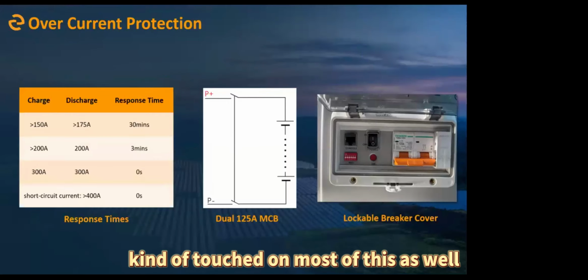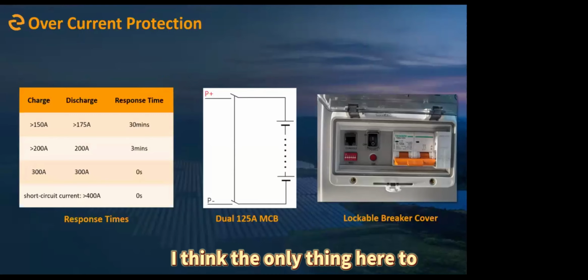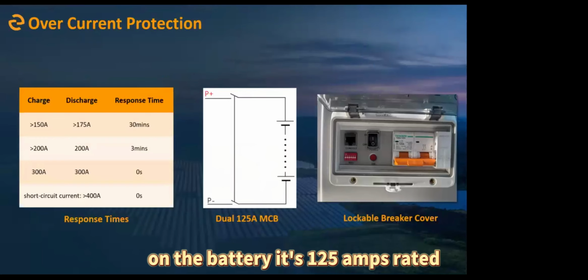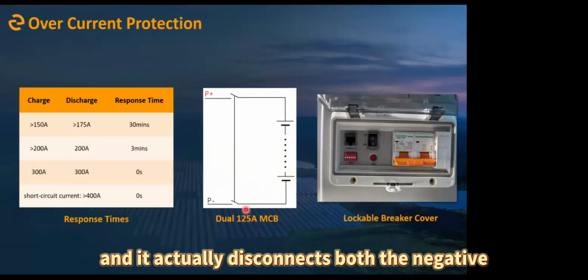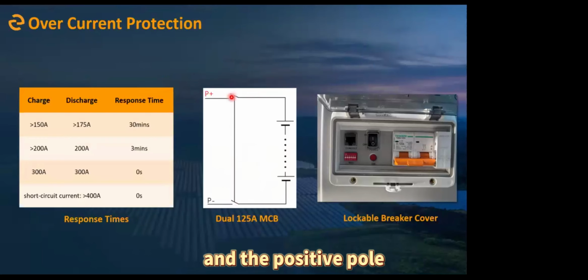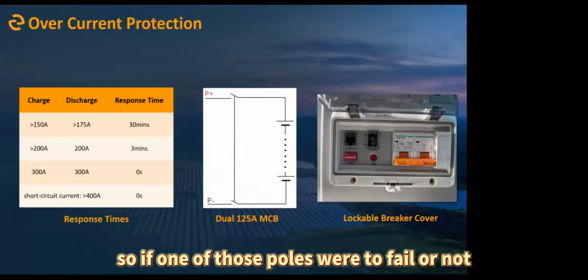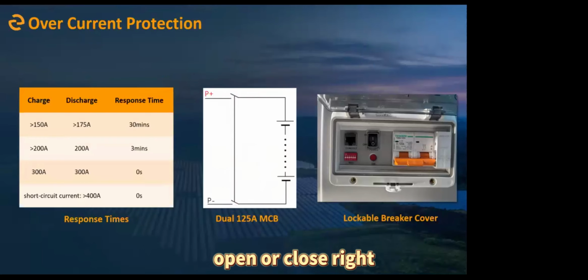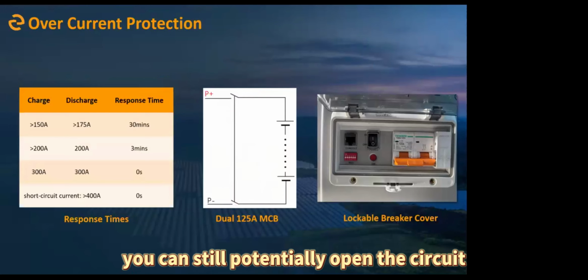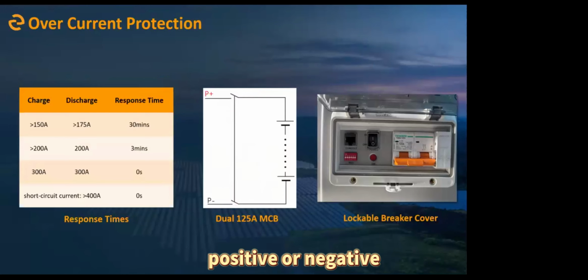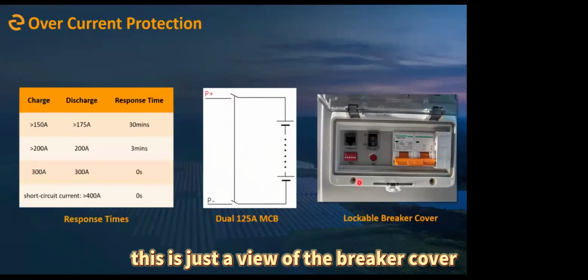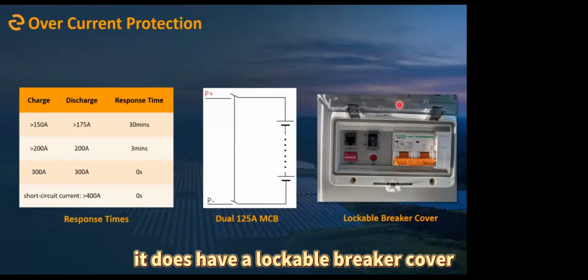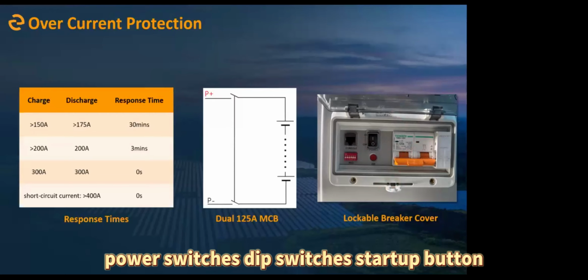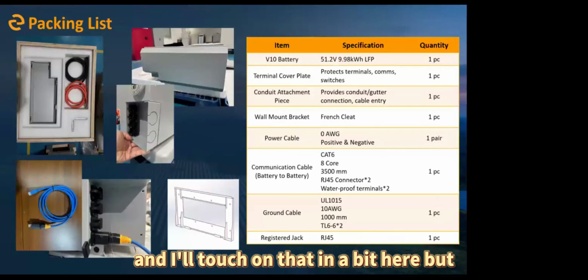Kind of touched on most of this already. I think the only thing to recap here is the circuit breaker on the battery. It's 125 amps rated, and it actually disconnects both the negative and positive pole. So if one of those poles were to fail or not open or close right, you can still potentially open the circuit with just one of the two poles. This is just a view of the breaker cover—it does have a lockable breaker cover. We can see the little breaker there, power switches, dip switches, and startup button, which I'll touch on in a bit.